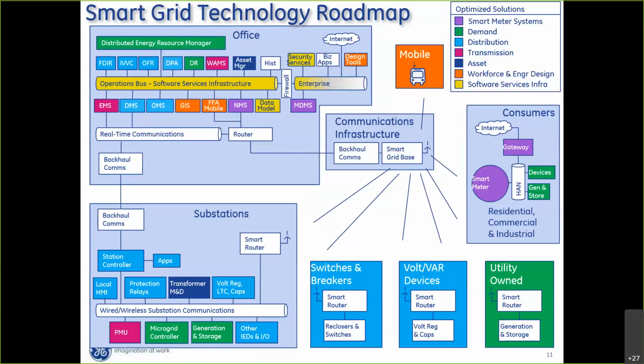Let's look at the light blue boxes. In the upper left, you have the office and the control center. The top four light blue boxes are software applications that run on the distribution management system. Below that, the DMS and outage management system are systems. We go down to the substation and see relays, the station controller, which we call the data concentrator. We see applications running not just in the control center, but also at the substation level. We've distributed the intelligence—these are volt/VAR control, fault detection, isolation, and restoration, which can run at the substation level.